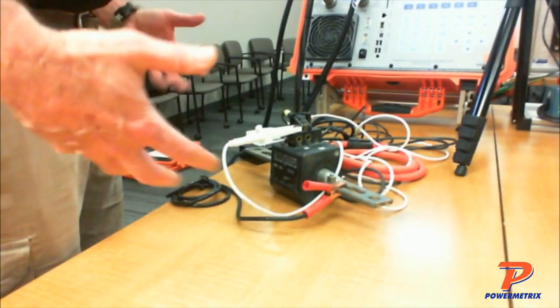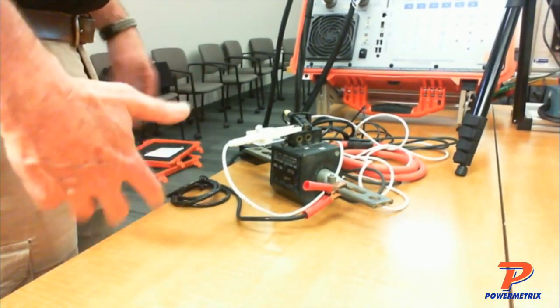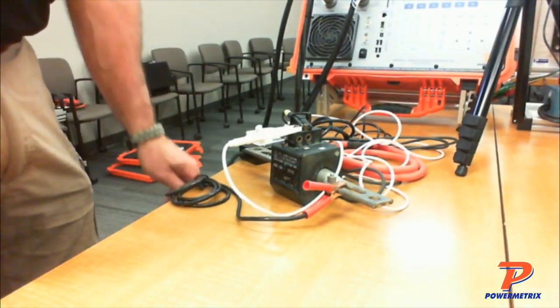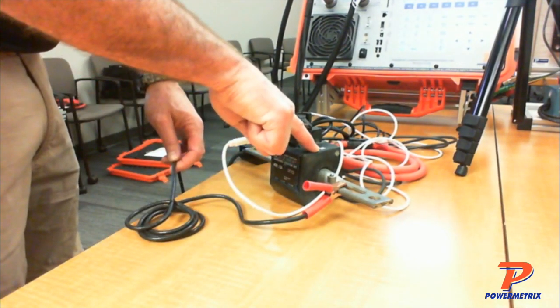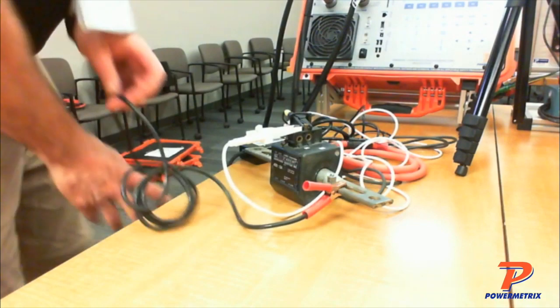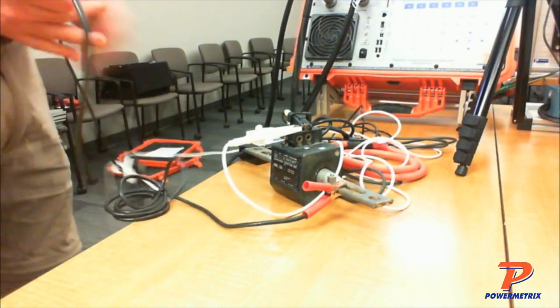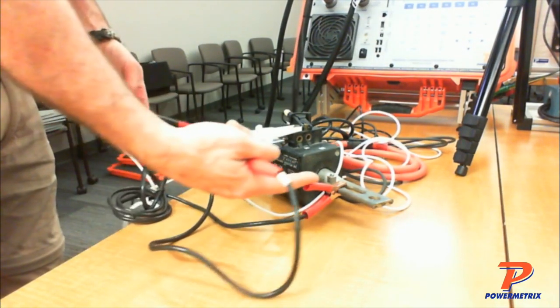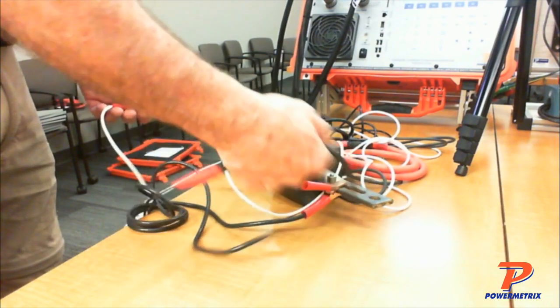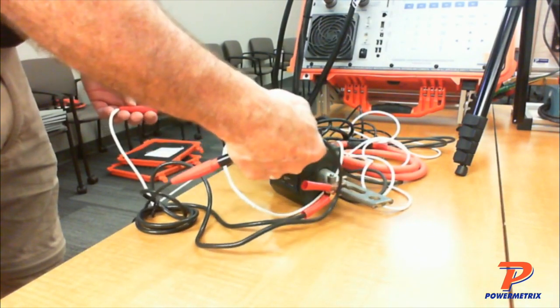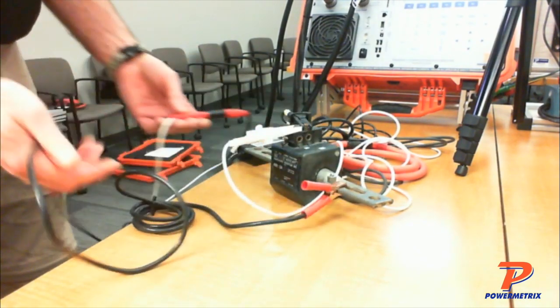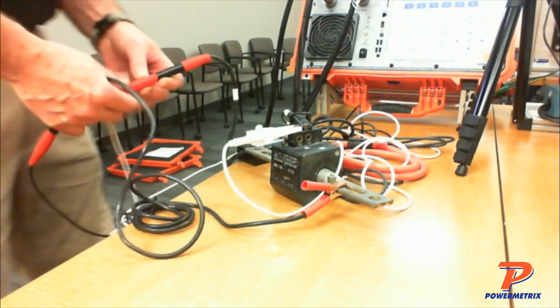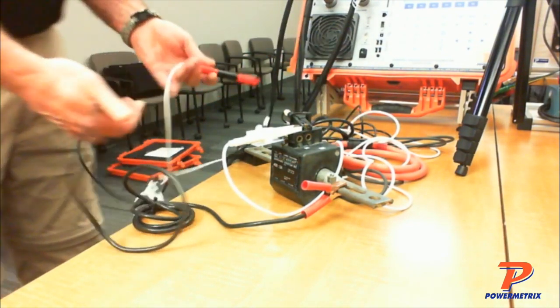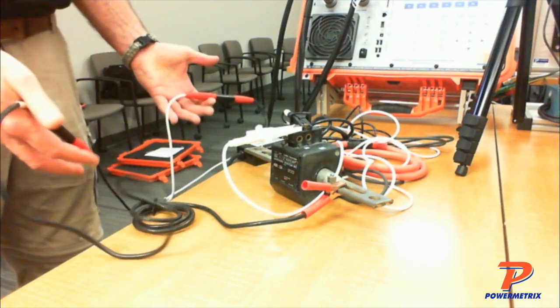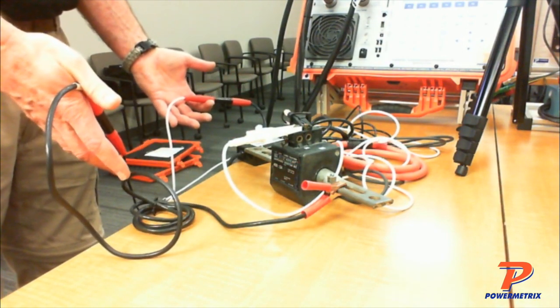Another thing that usually gets people hung up, and you'll only do it one time, you'll get a polarity reversal on it if you're doing these tests, is with the drive. So I'm over here on the dot side of my CT. I've got my drive side. I've got a drive and return on here. So my drive is over here where it should be, because that's where I would normally have my connection coming into the CT on the drive side, my hot side. On the return side, I come over here and that's exactly what I've got. I've got my return, my white cable is over here on the return leg on my CT, okay?